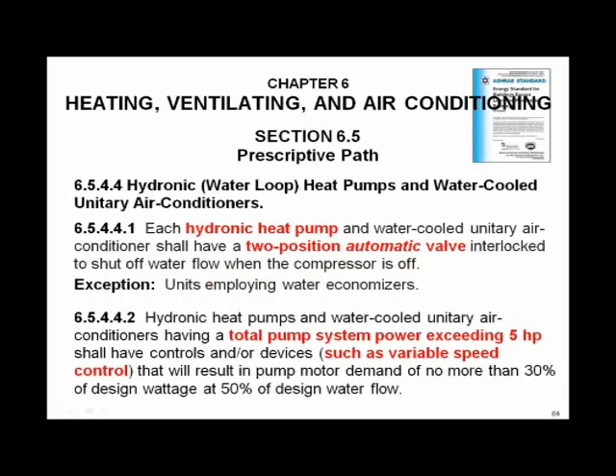That's simple. If you look at water source heat pumps, nothing really new here. You've got to have two position valves, and then they even become variable flow. So there's another comment you need to be aware of when you start looking at condenser piping and water source heat pumps. Look at the paragraph on variable speed. Any system over 5 horsepower, you've got to look at if you can get 50% turn down.